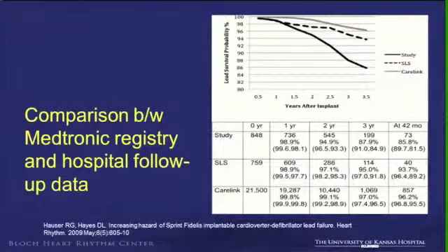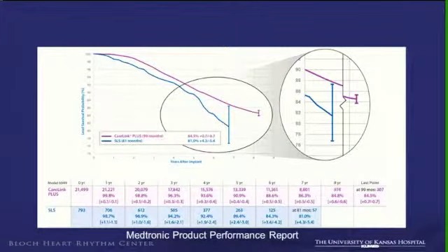And as I mentioned earlier, the comparisons have to be made by real life and product return analysis and actual studies. So if you can see, there's a significant difference in the projected survival of the leads. And this is as of May 2013. So this is the return lead analysis and the CareLink data. It's not increasing, but there is a kind of plateaued effect, or the same rate of failure of the Sprint Fidelis leads.